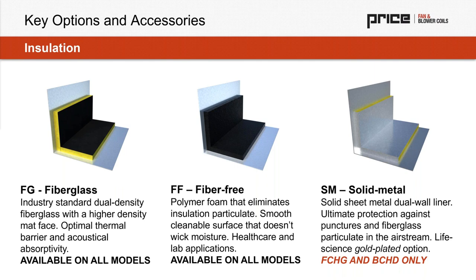We may see less sound breaking out of the casing, but we will see more sound reflecting out of the return. And usually that yields a louder application in general. So that's my word of warning and rule of thumb. If it's a ducted application, the solid metal liner is the best option for acoustics. For open plenum returns, it might in fact be the worst option.